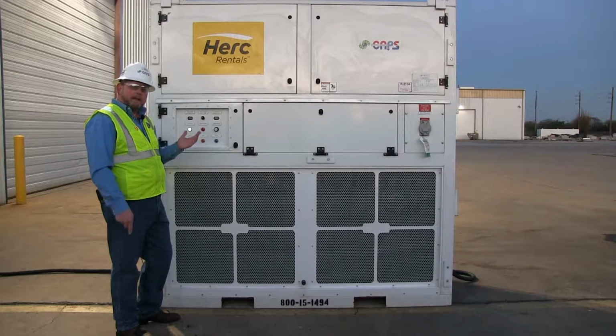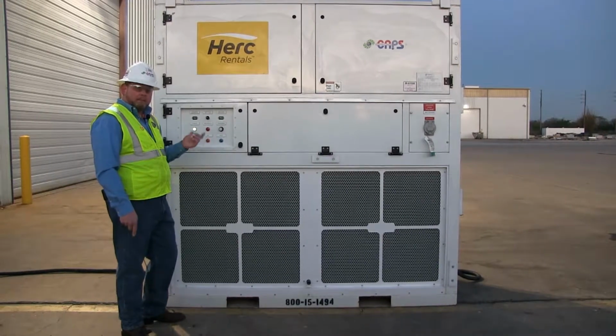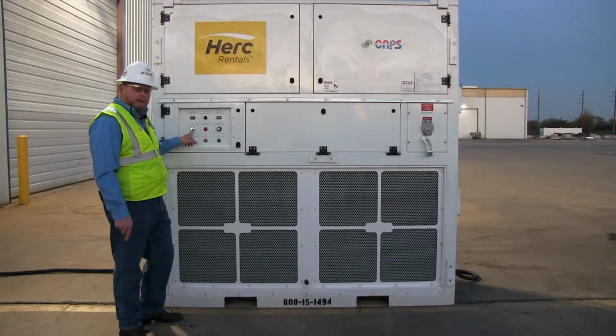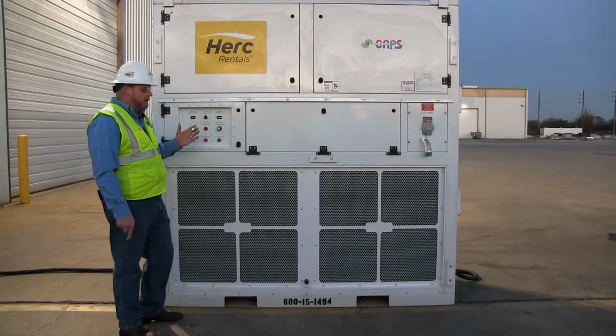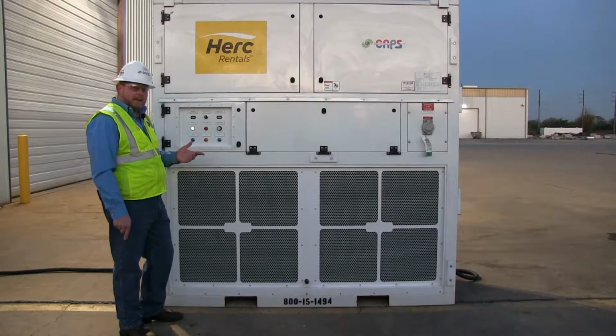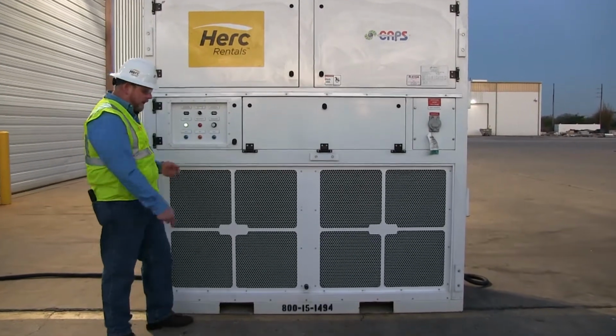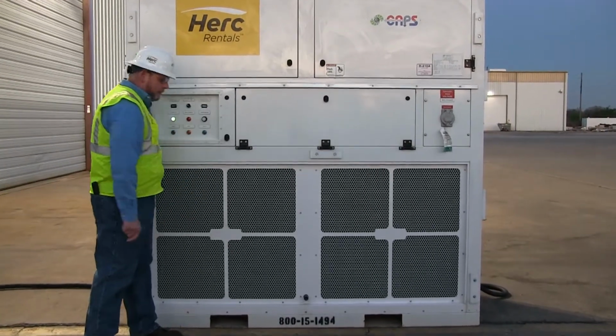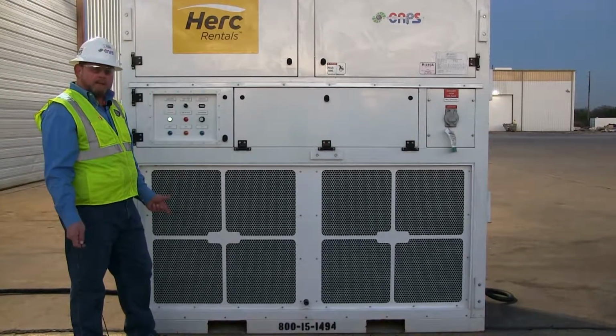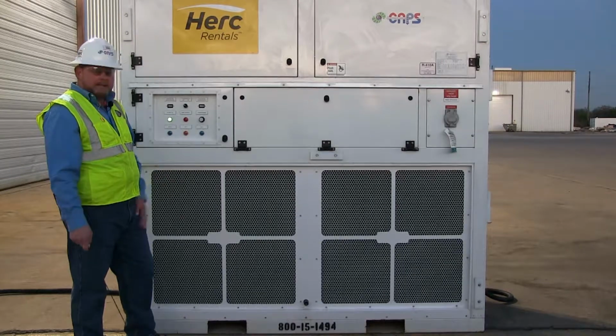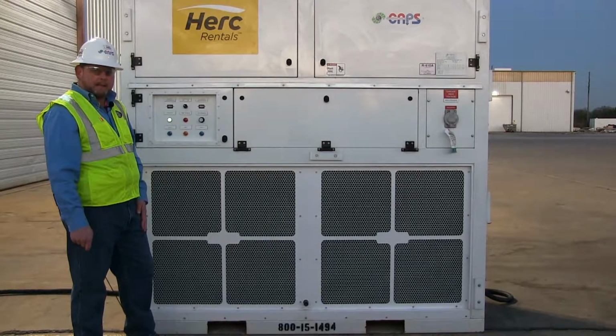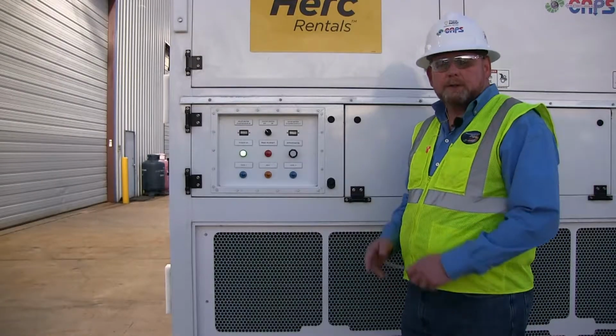We've got the unit tied into the tent wall. We have power on it, as indicated here by our power light. We've got the machine ready to start. One last item we've got to make a decision on is the condensate drain connections here at the bottom. You have the choice of having a gravity drain on it, or the unit does have a built-in integrated condensate pump. Okay, we're going to energize the unit now.